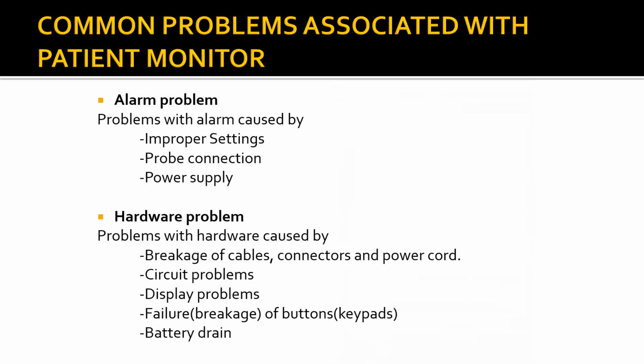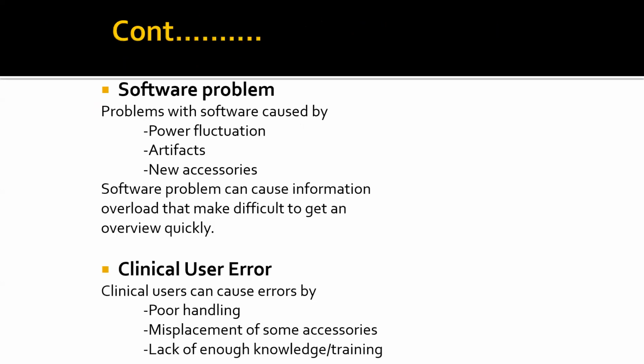Normally you're going to see problems caused by alarms from improper settings or a probe connection that is not connected properly. Power supply problems can be due to battery failure, and you're going to hear an alarm for battery failure. Then hardware problems are caused by cables, circuit problems, display problems, failure of buttons or keypad, and battery drain. Software problems are basically due to power failure. The patient monitor itself has a software problem and fails, cannot turn on, doesn't reboot.